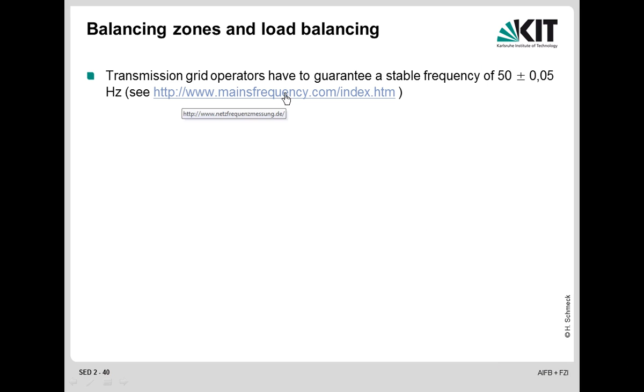So that's the mains frequency, and here you see the current frequency that we have, 50 Hertz. It should adjust to the current frequency. Certainly the current frequency- yeah, you see, now it's going down. Now it's the measurement, it's not exactly 50 Hertz at the moment, it's 49.97, and you see that we have a quite low frequency.